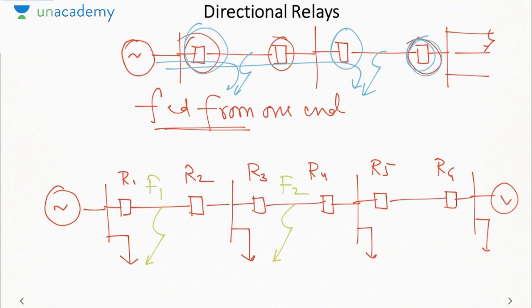Now when the fault occurs at F1, which of these relays must operate? Since the relay nearest to the fault is R2, R2 must operate. But if you see, the current flowing into this fault will be something like this, since it is fed from both ends. Like this. So that means this relay will also be encountering overcurrent, which is an undesirable condition, and hence this relay can also operate, but it must not operate. Only the relay R2 must operate. So we must design a relay such that the relay R3 does not operate under such a condition. That means just the overcurrent protection is not sufficient in case the source is fed from both ends.